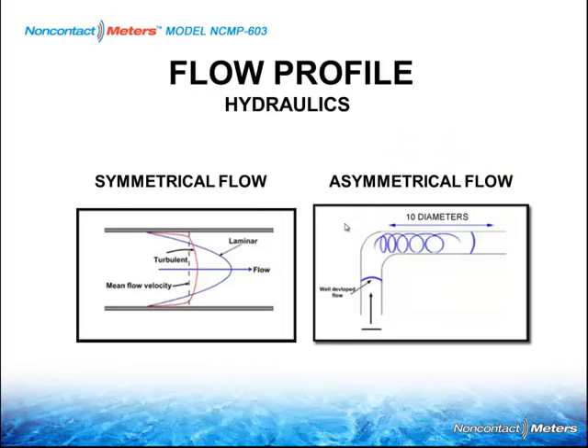Now another key thing with ultrasonic transit time flow meters is that they do require some straight run of pipe for optimum performance. The magic number for a symmetrical flow profile is your traditional 10 and 5, or 15 pipe diameters between elbow to elbow for flow rates that are around 10 feet per second. Don't know your flow rates? Well, generically speaking, most pipes and pumps are sized for around 7 feet per second velocity. So that's just your rough gotcha there. So 10 feet per second is typical.